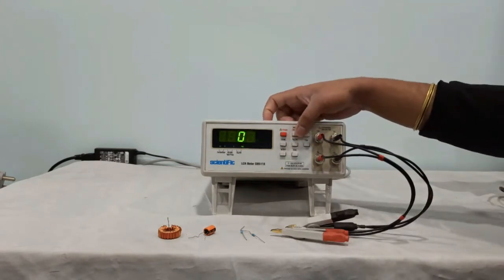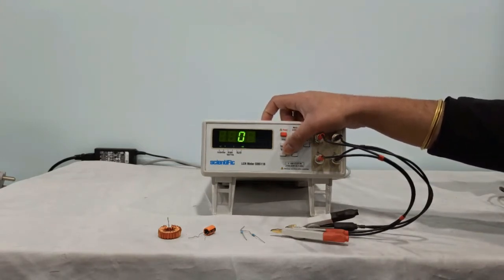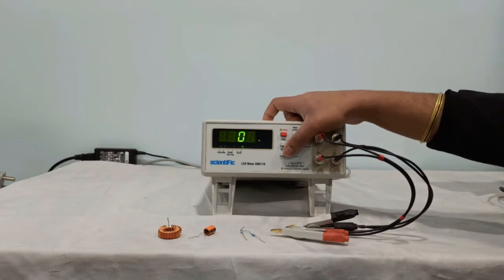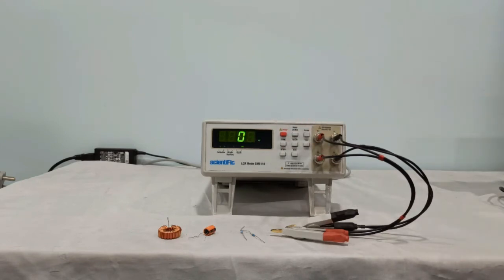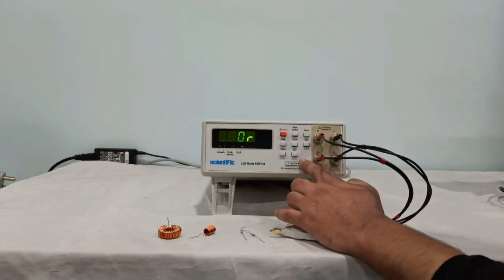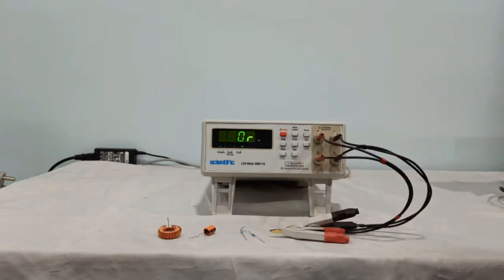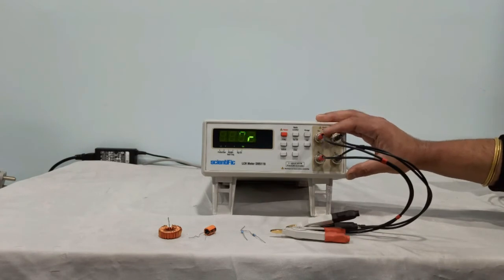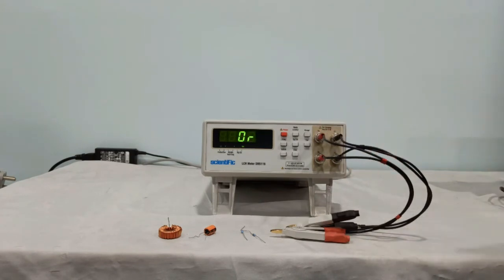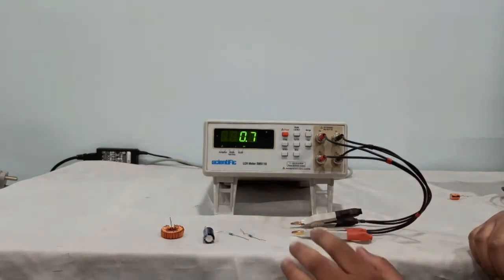Next we have Q, D and phase. Q is for quality factor, D is for dissipation factor and theta is for phase angle. Next we have bias. This is for providing 2V polarizing voltage for use when measuring electrolytic capacitors. Now we have a few components with us. We will see measurements on this unit.